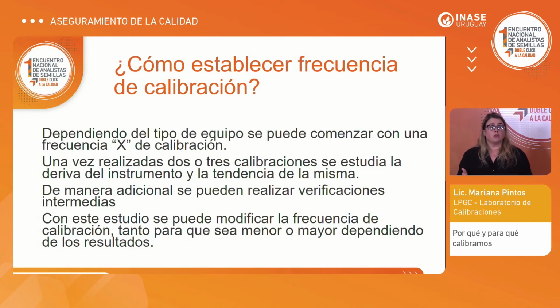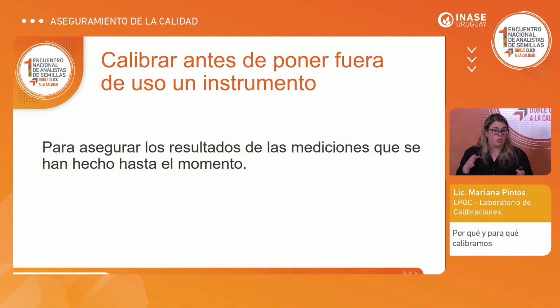Sometimes you can have mid-term verifications through calibrations when I'm not familiar with the equipment or with the brand, and so we can see how the equipment is performing. After the study, we can do two things. If the equipment tends to drift from the right measurement, then we need to calibrate the equipment more often. But if the equipment is stable and there is no regulation requiring that I conduct a recalibration, I can extend the calibration term.